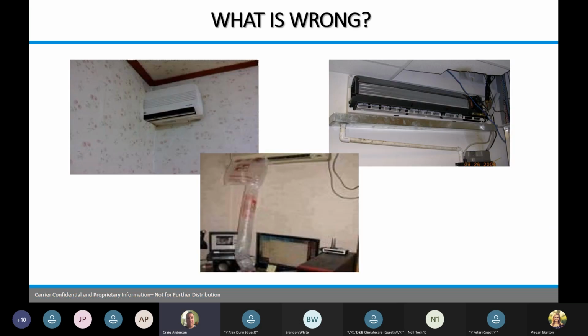So a couple pictures. We always like to throw in some pictures guys have taken on job sites. Somebody tried to do zoning with this unit, built a wall and shoved it in between. Good luck servicing it. This one here, we definitely have some problems. It's probably freezing and they had to put an extra drain pan under it to compensate for dripping water or freezing. You'll notice it's quite tight to the T-bar ceiling, so airflow was probably one of the biggest issues on that one. This one here with the bag, we're not 100% sure what they were trying to accomplish on that one.